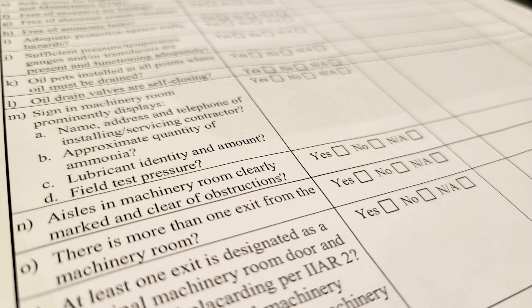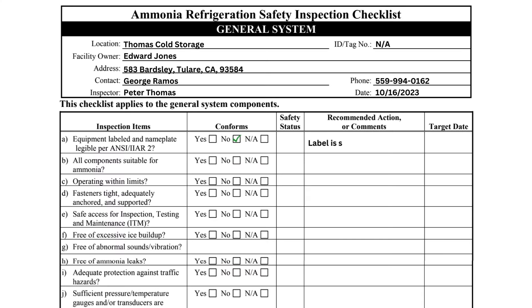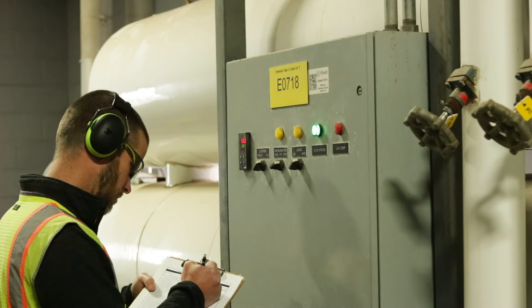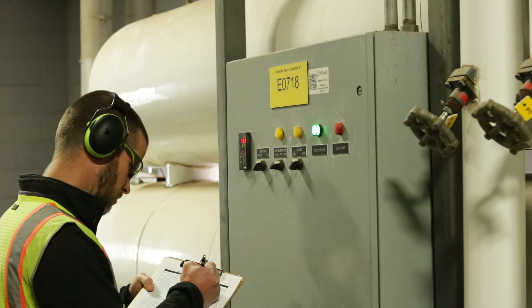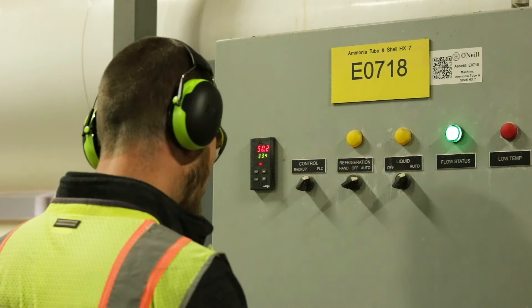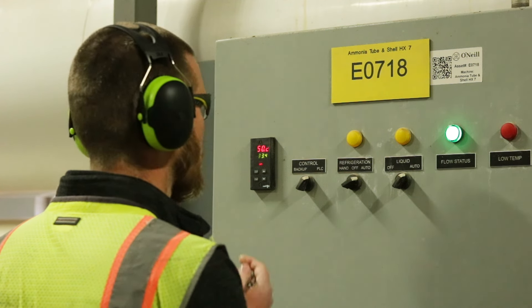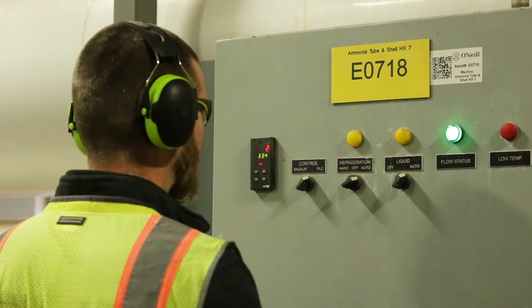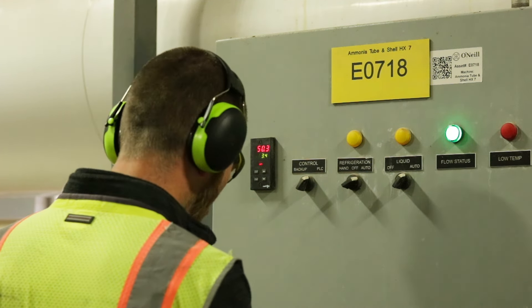Some questions may not be applicable and should be answered NA. Item A asks if the equipment in the system is labeled and has legible nameplates. A proper label consists of the component name and ID number. Since this shell and tube heat exchanger label ID number is so small, that should be marked as an item to be addressed.